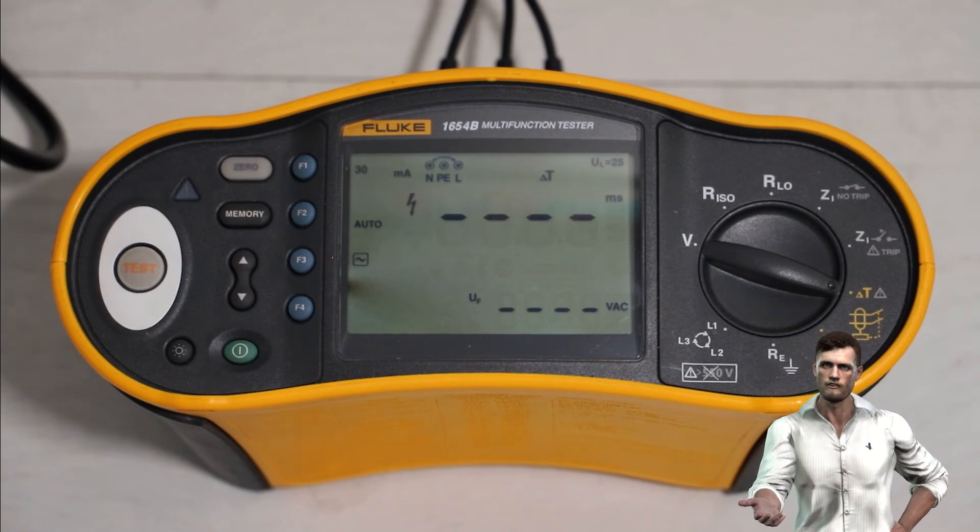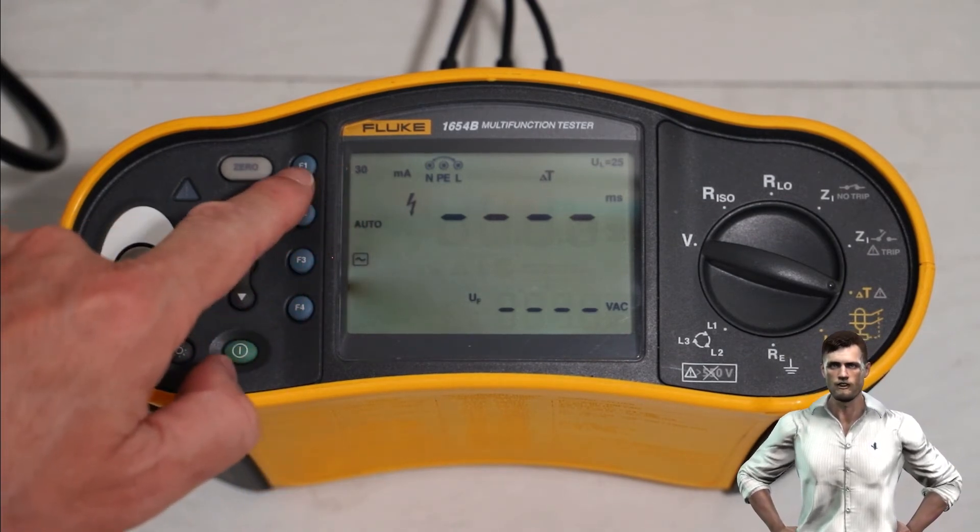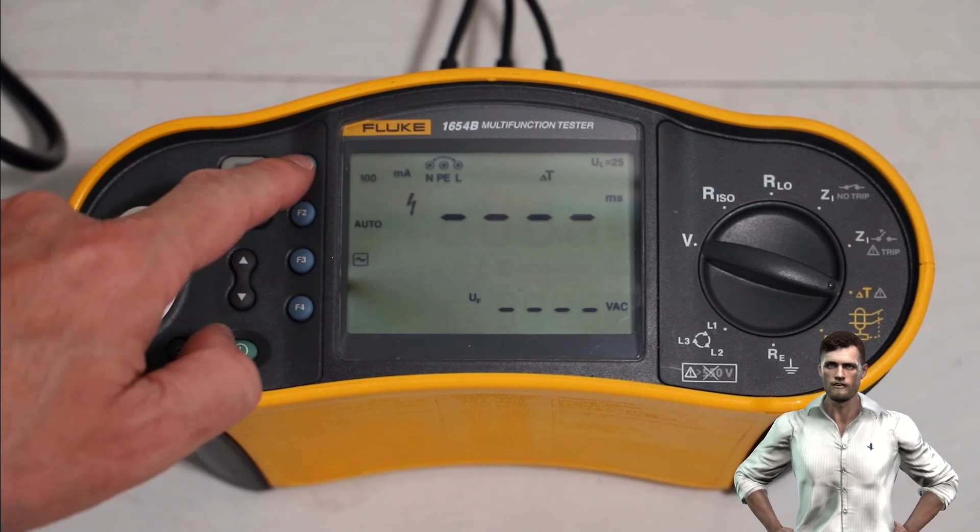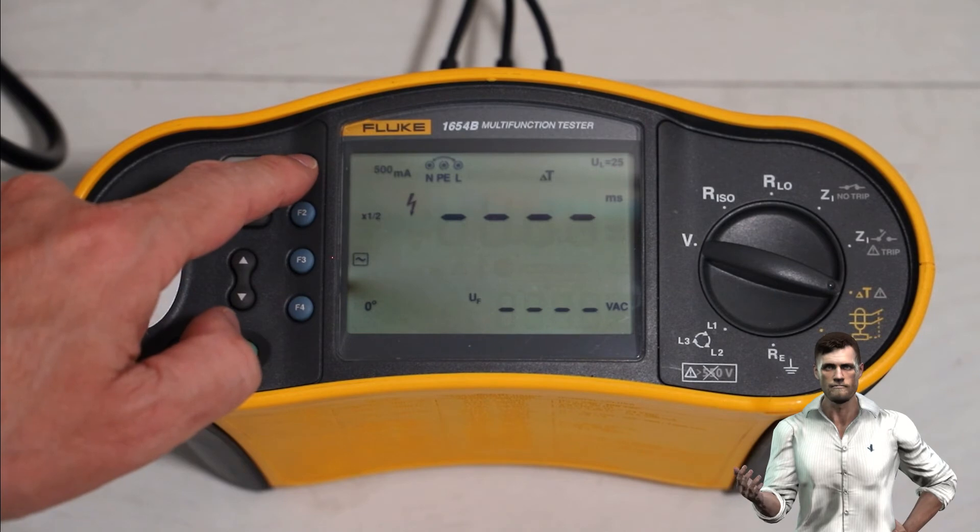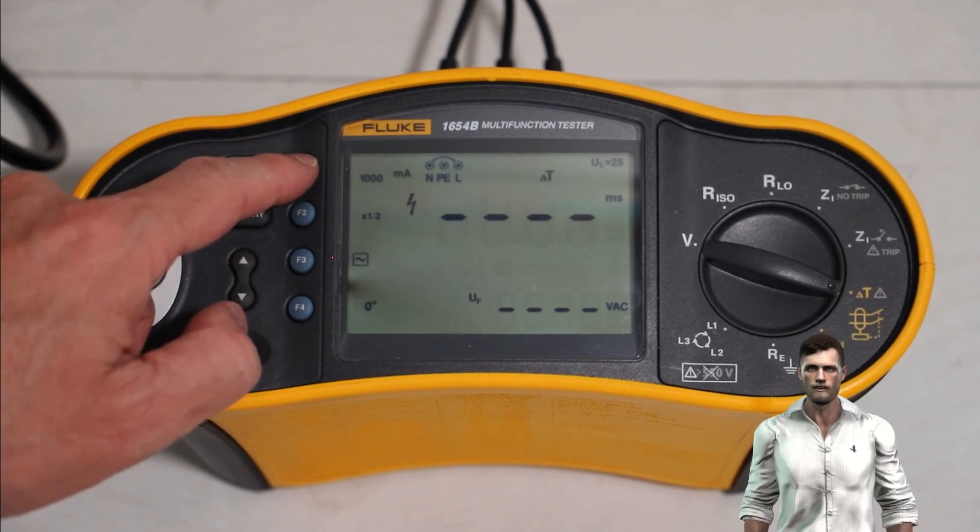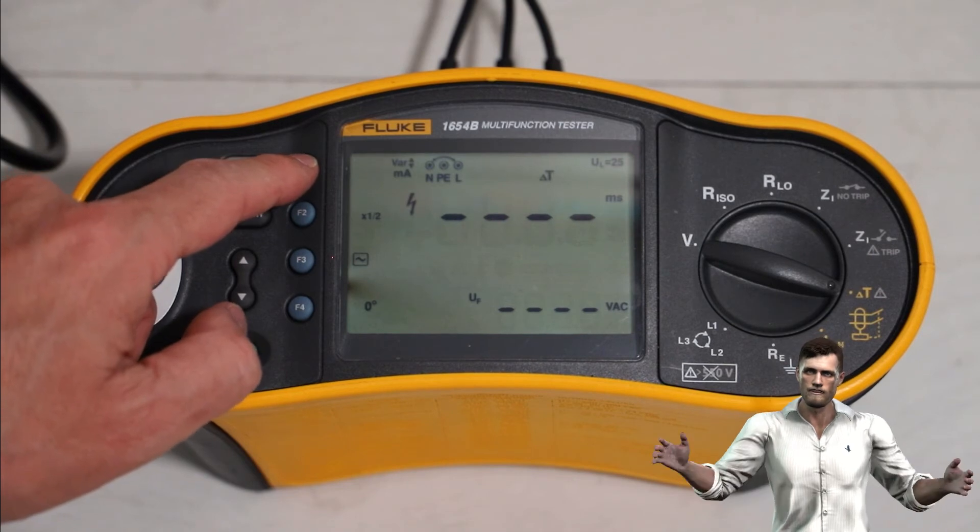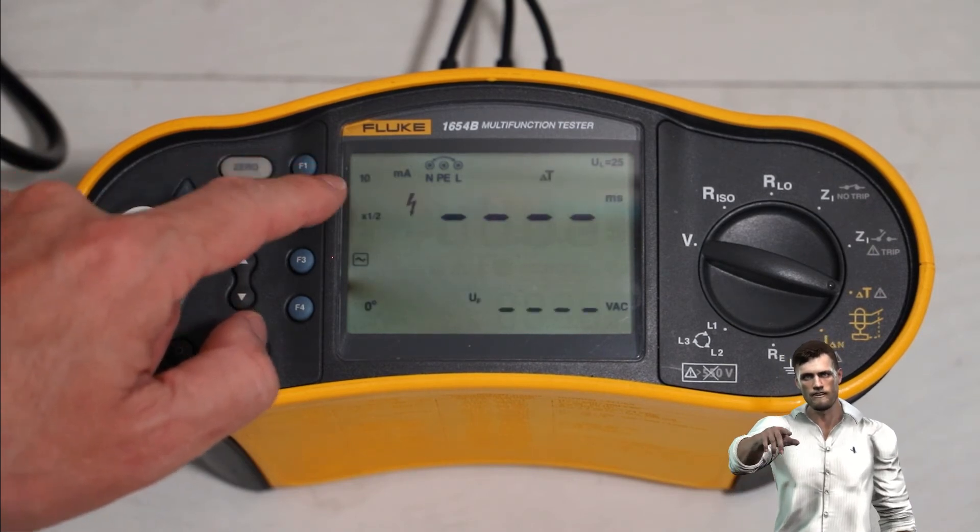With F1, we can select the nominal leakage current of the differential protection between standard values such as 10 milliamps, 30 milliamps, 100 milliamps, 300 milliamps, 500 milliamps, 1000 milliamps or if we wish, we can configure a custom value. In this case I am going to test a typical 30 milliamp differential protection present in many houses.